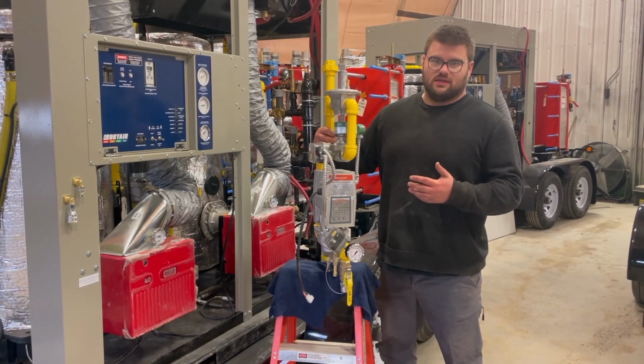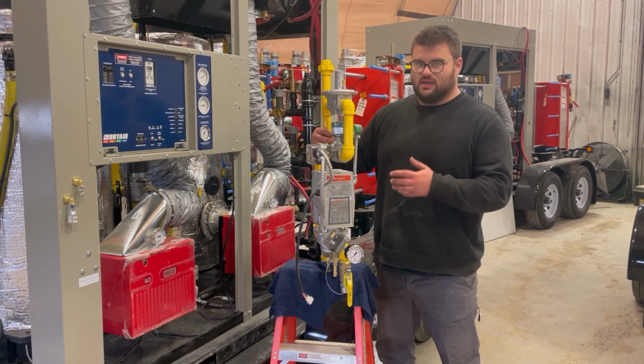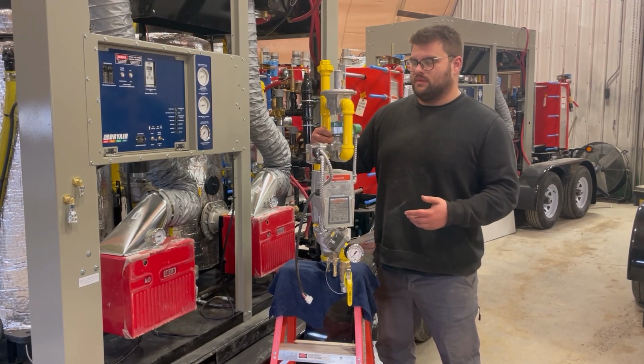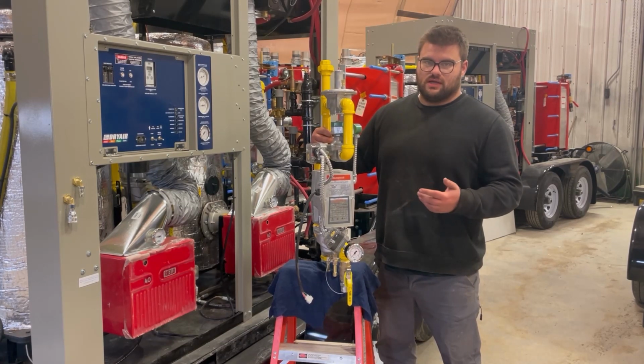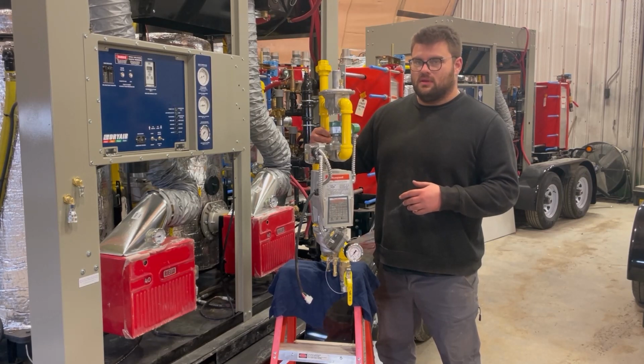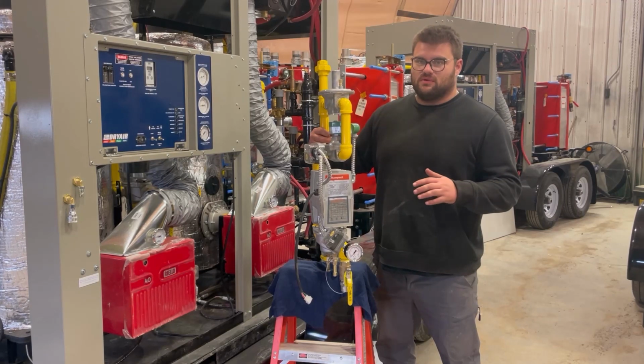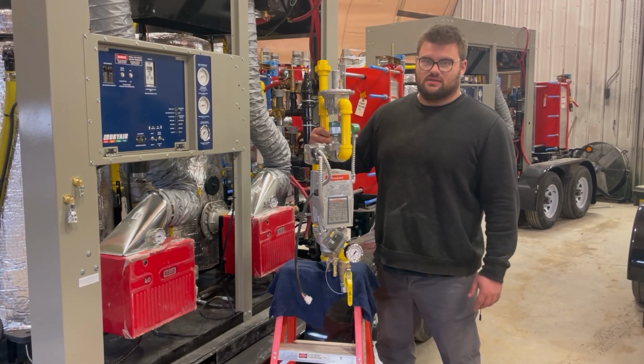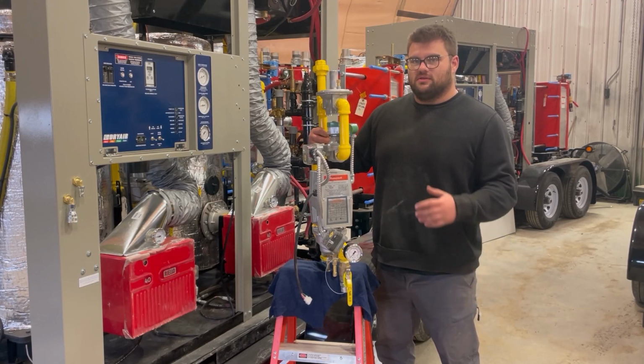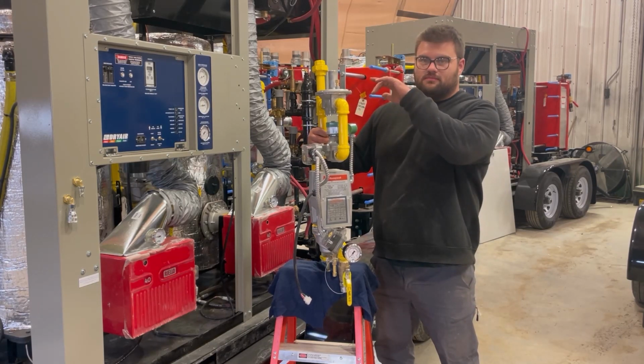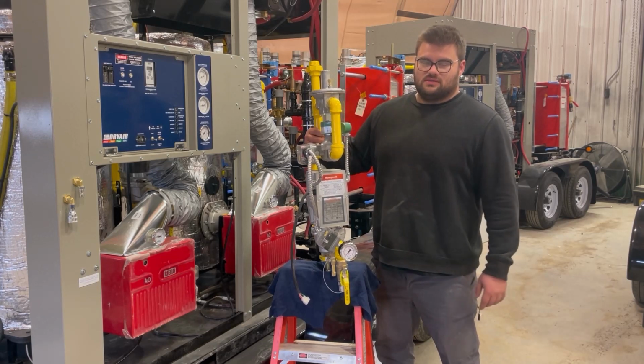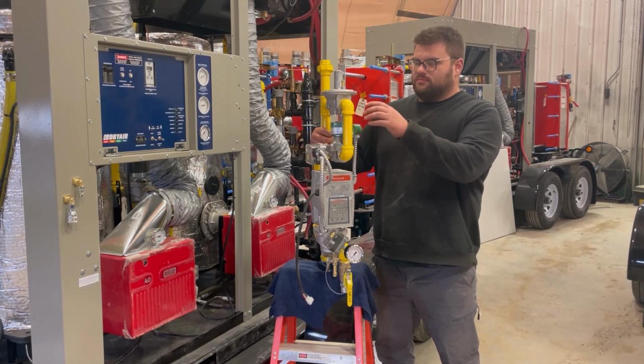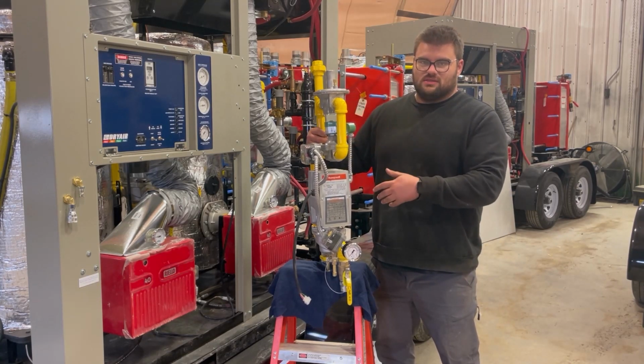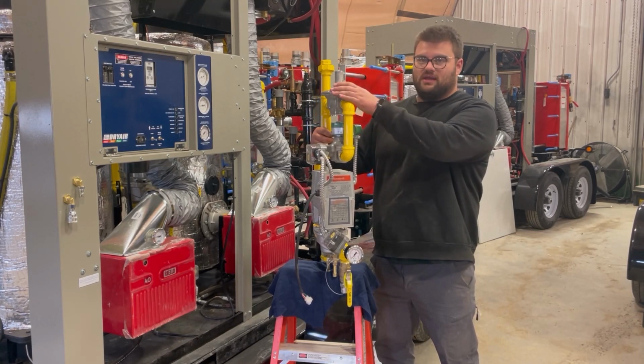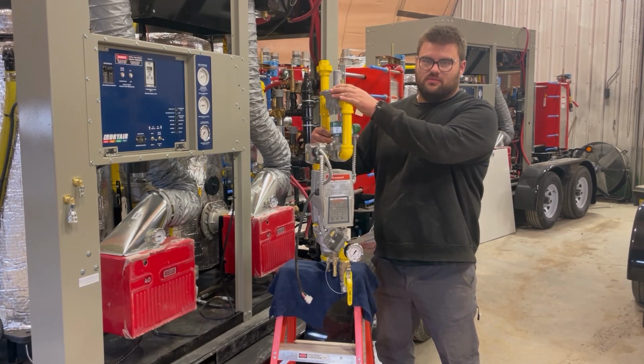Your main gas line into the unit branches off into 2 gas streams, one for each burner. These gas streams are used for either natural gas or propane. We like to have at least around 14 inches of water column for gas at all times. There's a main gas line gauge coming into the unit, and it branches off and separates that gas into each one of these. You have a regulator to fine-tune the gas going to your burner.